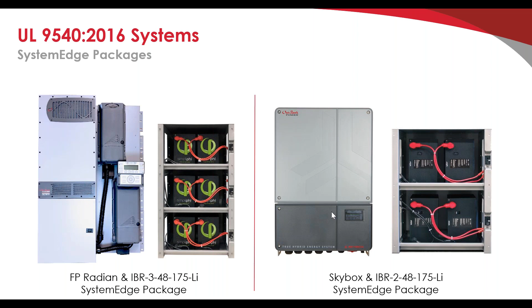So there will be a label for an inspector to check to indicate that this is indeed a UL 9540 system, and that's backed up by the Declaration of Conformity and respectively the test report for UL 9540.